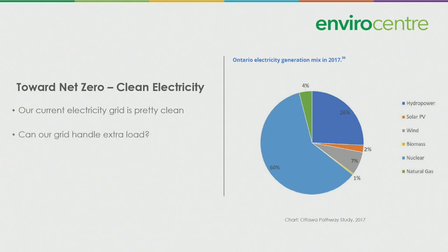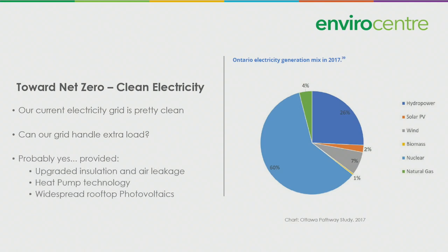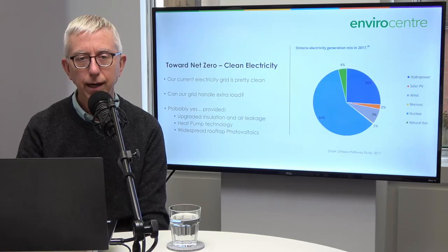The question is, can our grid handle the extra load? If we're going to shift everything off of producing heat directly with natural gas and start producing it with electricity, are we going to be able to handle that? Probably yes, I would say, provided that we also upgrade insulation and air leakage in our buildings, we adopt heat pump technology, and we install photovoltaics on a widespread scale on rooftops. There's a lot of flat roofs out there that have nothing on them but HVAC equipment.